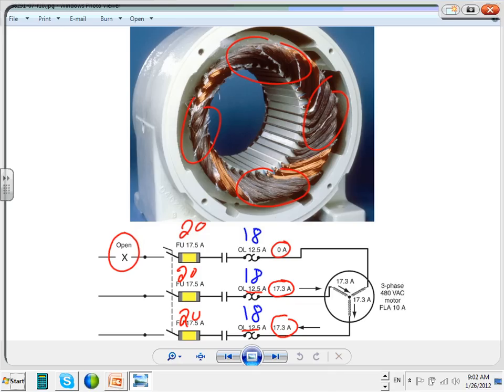Do you think the 18 is going to wake up when 17.3 is going through it? No, not fast enough to stop the burn that's happening to the coil. So you lost not all the coils. It doesn't matter if you lose part of your coils inside your stator, you're dead. Your motor has to be rewound. So you have just lost $200, $300, $400 depending on the size of the motor. Because of what? Because of a tiny little overload that you neglected to size properly. Short circuit. Thank you. This is overload and single phasing.